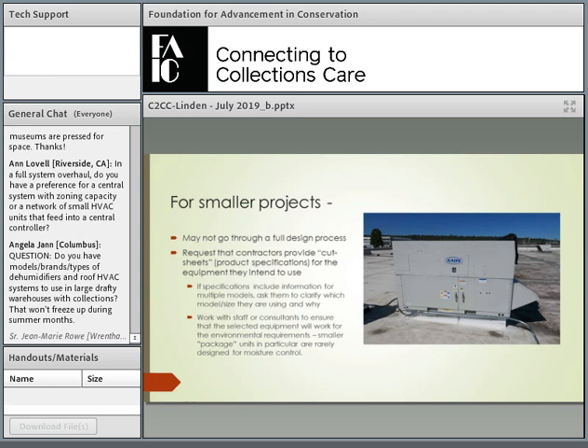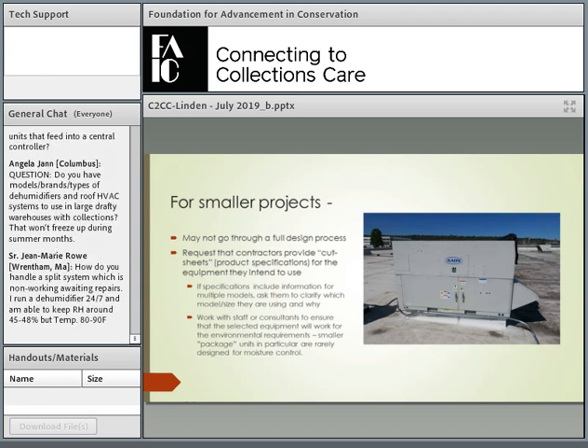they're not always as good at the moisture control side of the design. So they may do very well in terms of getting you a piece of equipment that does well with temperature control, with being able to cool, but not necessarily humidify or dehumidify. That's where that critical review of their proposal for equipment comes into play, so that you can talk about: this may get us the temperature that we need, but does it get us the moisture content that we need? Is it capable of controlling for dehumidification and/or humidification?